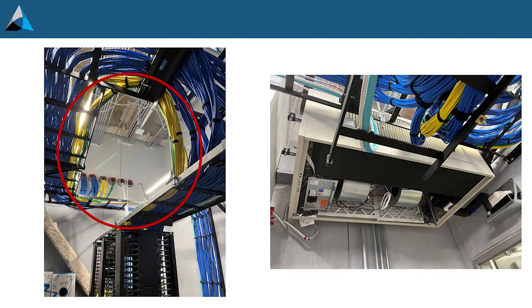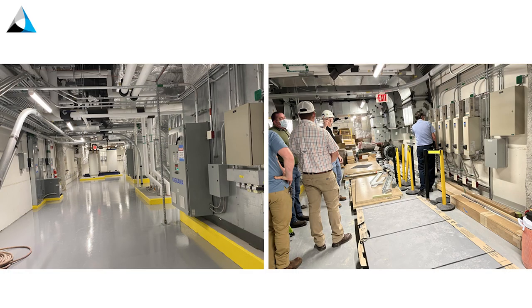We did do a design review and caught the fact that in this IT room there was a big open space in the cable tray racks — about fan coil unit sized. We said they were missing the fan coil unit, nobody really reacted, and so they ended up jamming it against the wall where you can't get at the filters and there's no airflow. Also, advocating for maintenance and storage space: this was one of the nicest mechanical penthouses I've ever seen, but a week later doors were being stored there. Any room with open space becomes a storage room because nobody plans for where to store filters or replacement parts.